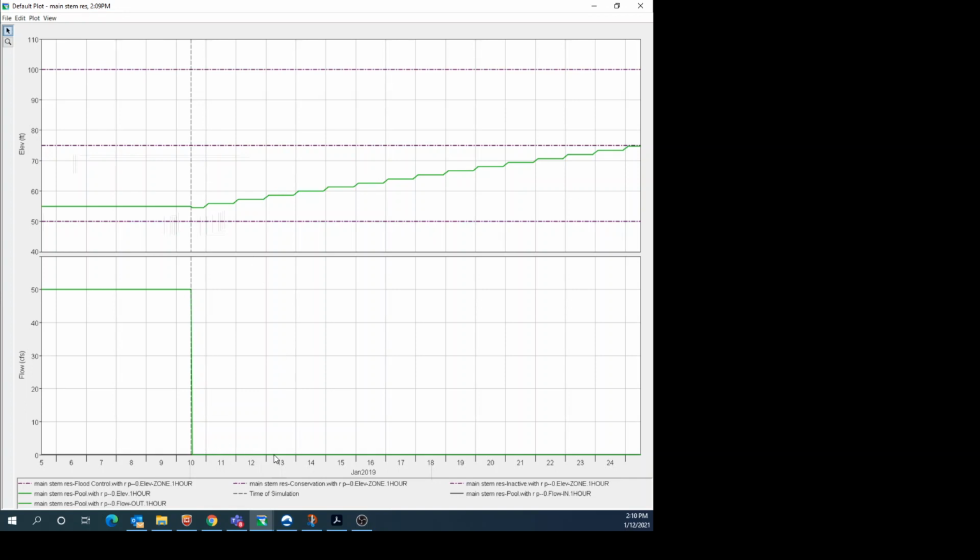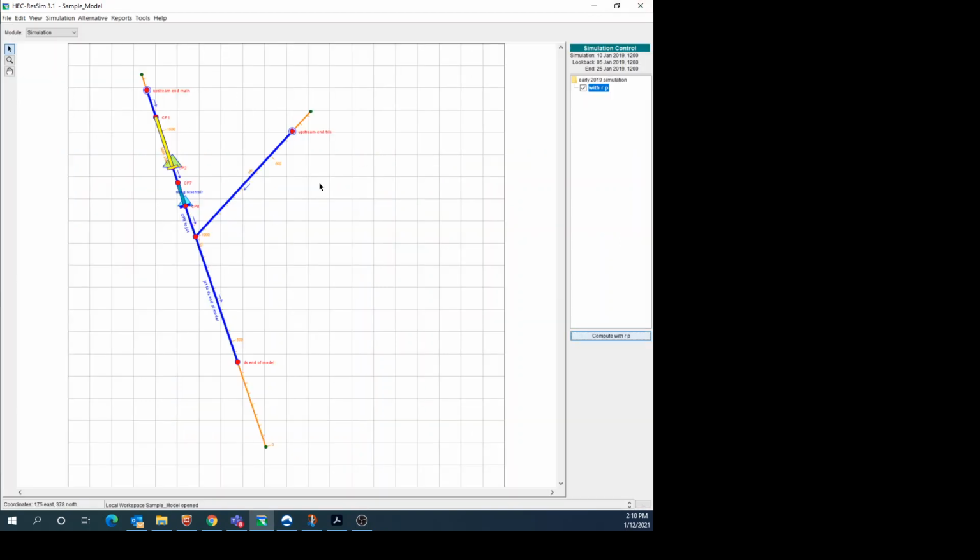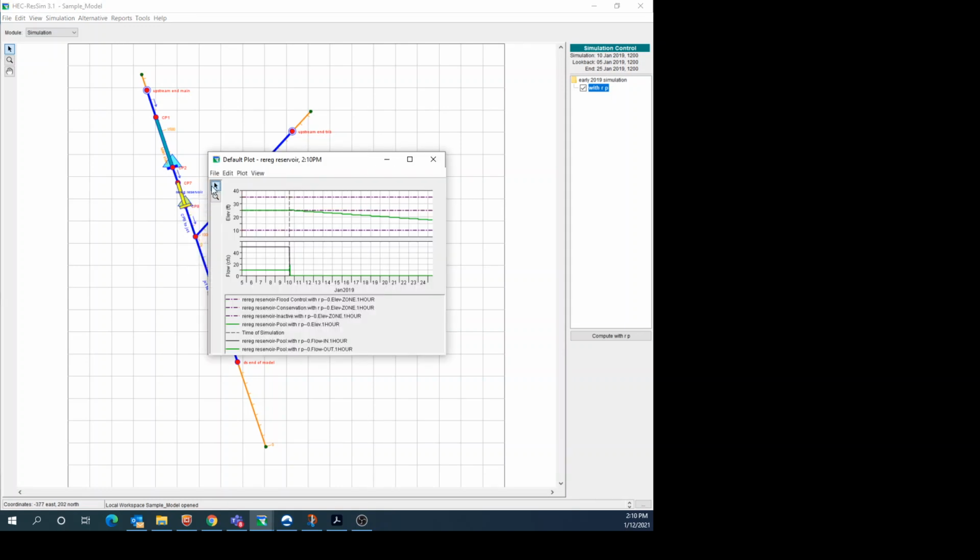You can see here that my inflow is very close to zero and my outflow is actually zero. But during the periods where I don't have pump back occurring from that downstream reservoir, the reservoir level is basically flat, which is what you would expect because inflow is just about equal to outflow. It's during these periods from 10 p.m. to 2 a.m. that I'm starting to get these rises, and that's causing a rising pool elevation. And you would expect just the opposite at the re-reg.